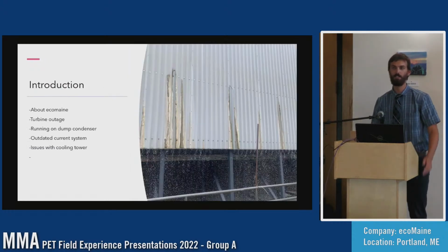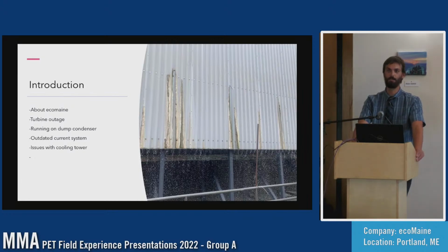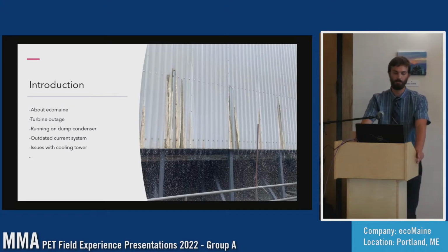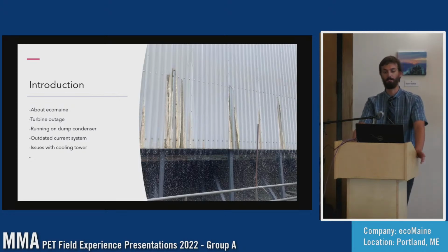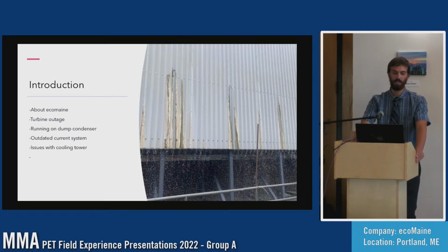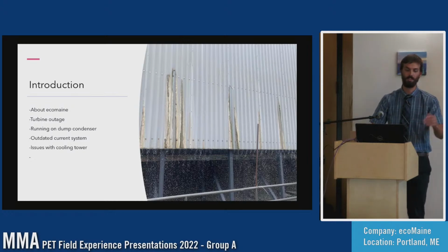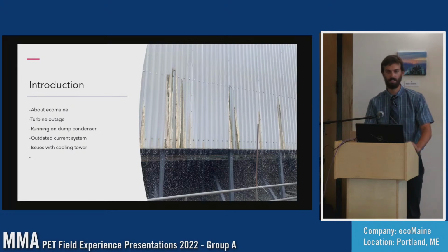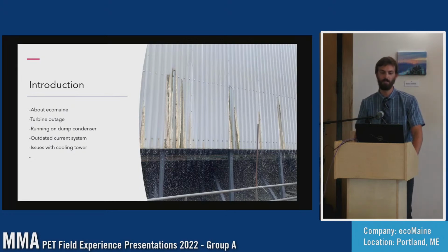So as an introduction, this summer at ecoMaine we had our turbine outage before the co-ops got there, and it went pretty badly. It ended up in quite a bit of insurance litigation, so what was supposed to be a 2 or 3 week turbine outage turned into a multi-month turbine outage. So we had to run on the dump condenser, which is what they normally do. It happens once every 7 years, and obviously we had a little bit of problems with it.